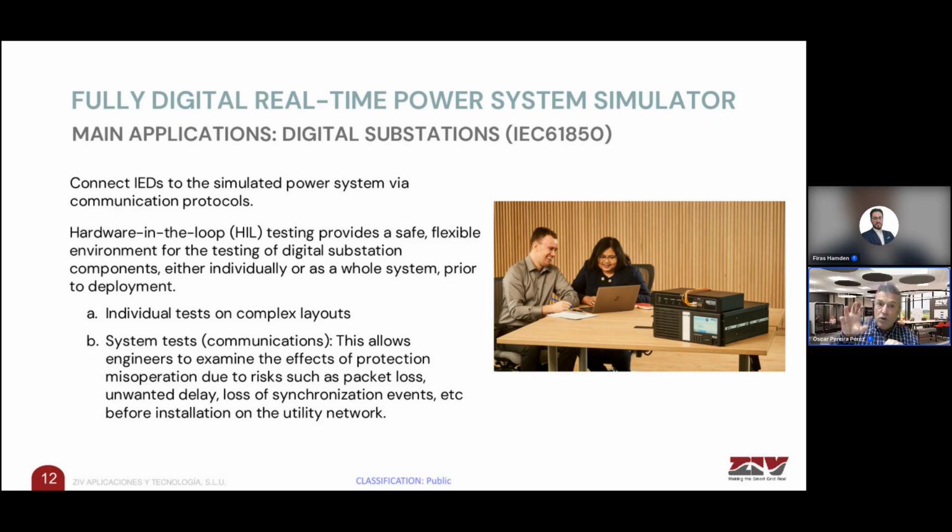We can, of course, include in the hardware in the loop our physical AVR, and we can test the behavior of our AVR in a situation working with 5 transformers in parallel, with no need to go to the site and to stress the machines, right?